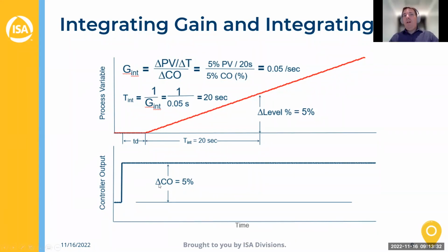So you're saying my step change might not be instantaneous because of a ramp in my VFD. That's what you mean, right? Yes, which is highly likely. Just about every VFD, the default is some sort of ramp. Yeah. So I will not take it out, because the VFD is part of the process response. When I do my step change, I may not have an instantaneous change like I see here, a straight break. I may see it slowly ramp up and then eventually stabilize. But I would still have the dead time of the process, right? This is how I will be operating it. The ramp will be there, so it's still part of the process. So I would leave it on.